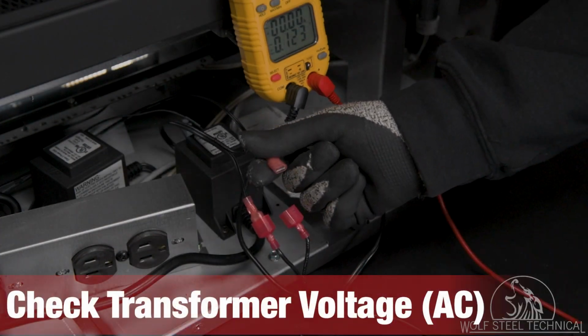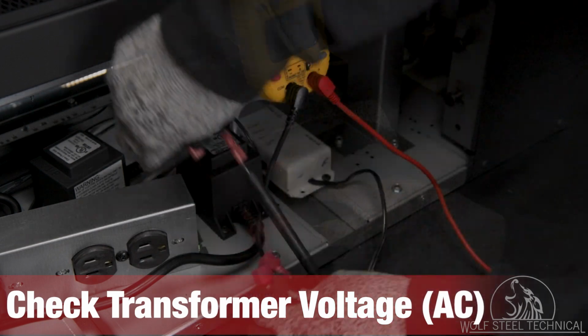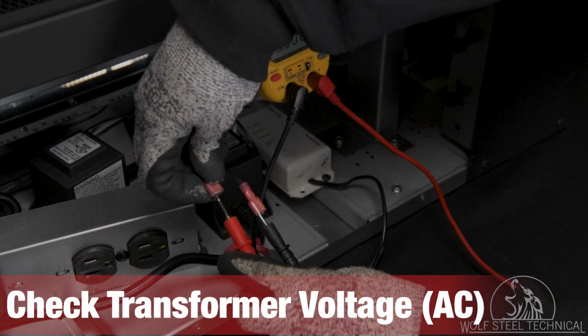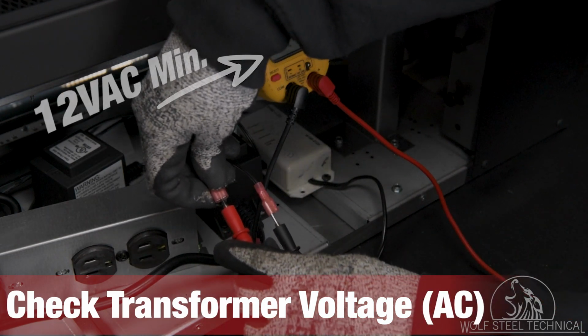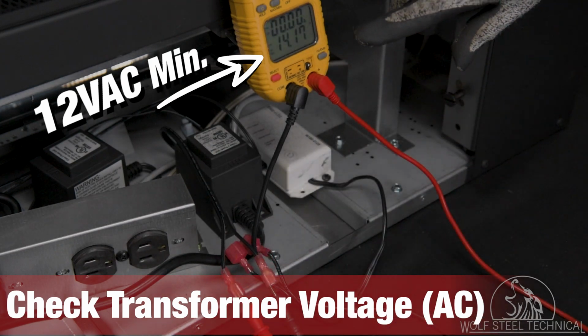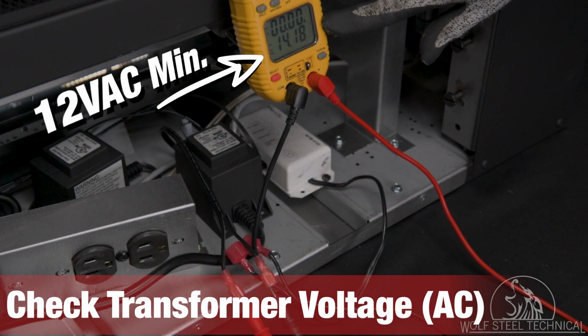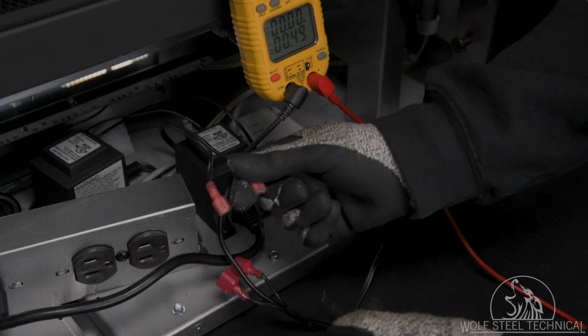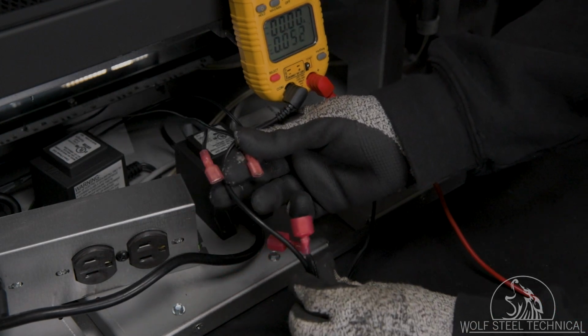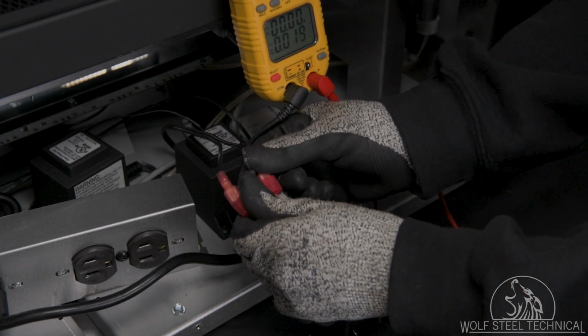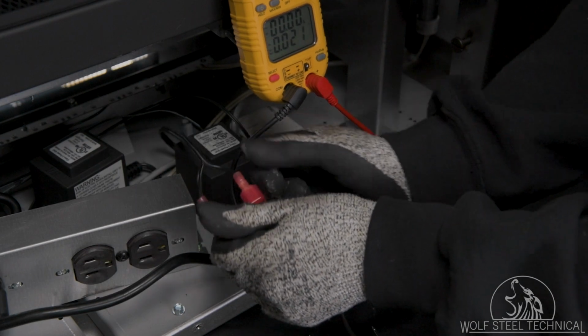After checking the receptacle, disconnect the transformer, placing the leads on either end of the connectors. The reading should be a minimum of 12 volts. Anything lower than this will require the transformer to be replaced. If you receive a reading at or above 12 volts, remove the multimeter leads and reconnect the transformer.